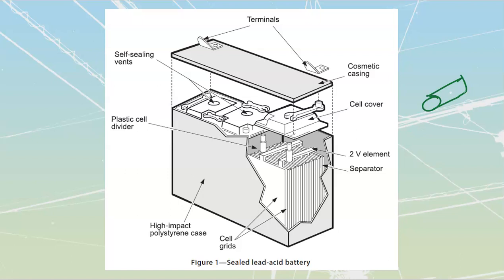They do have a better discharge than what we would have from the Nicad, which is why they supplanted them. First of all, they're lighter. Secondly, we can get more cycles out of them. They've got about double the capacity. Not nearly the same as our lead acid, so we do keep a lot of lead acid. Why not have a heavy lead acid battery inside of a piece of unit equipment? It's not like you're carrying it around. Inside of your hand tools, absolutely, we want to go lithium. But outside of that, lead acid is going to be fine because it is so robust.